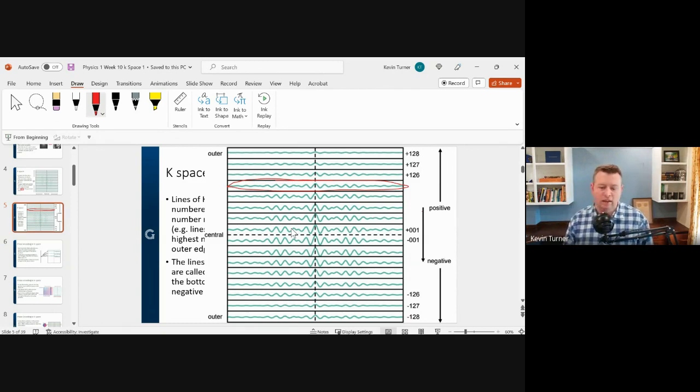When you have echoes that look the exact same, but they're in the wrong place in K-space, that is what motion artifact is. When a patient moves and their anatomy is no longer in the same spot, then the phase encoding gradient ends up putting the wrong information in K-space. The technical name for motion artifact is phase mismapping, because the computer put the wrong echo into the wrong spot in K-space. It thought it was the right spot, and it was the right spot until the patient moved. Now the patient's anatomy is in a different area. So what does the computer do? It compensates for this by putting that information across all of K-space.